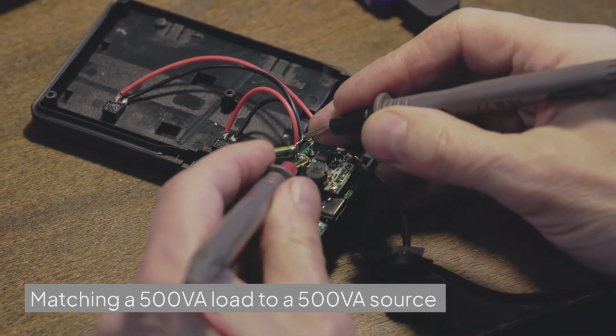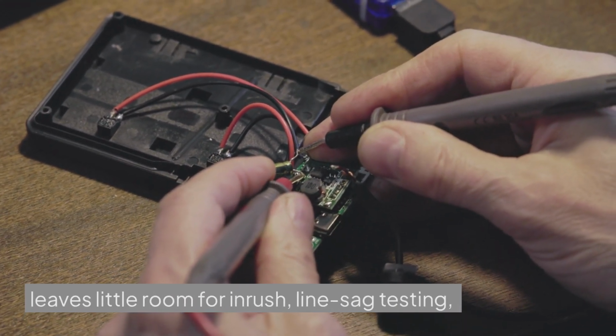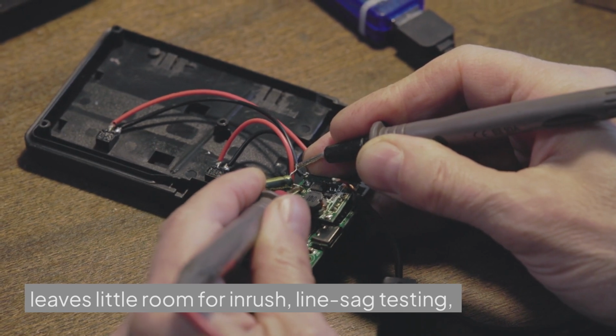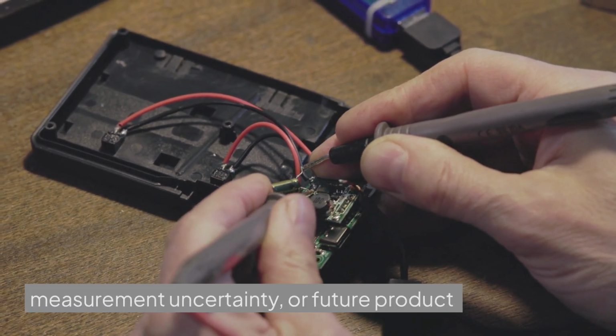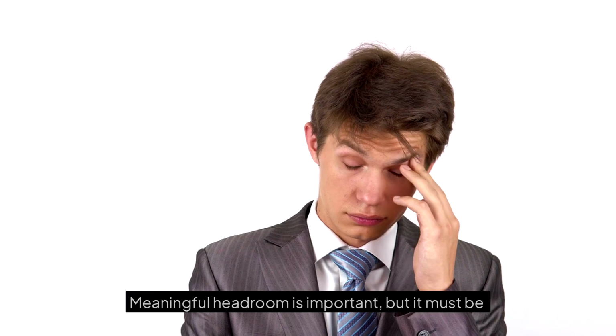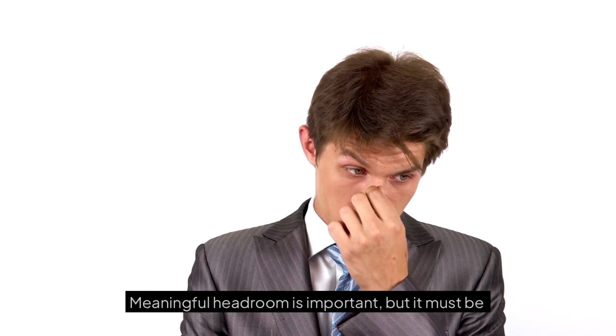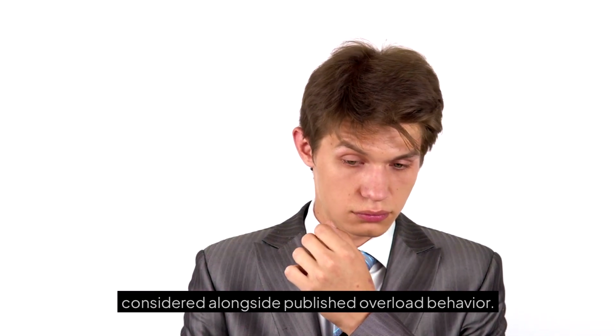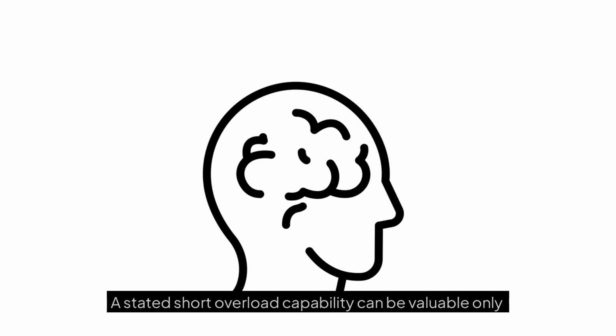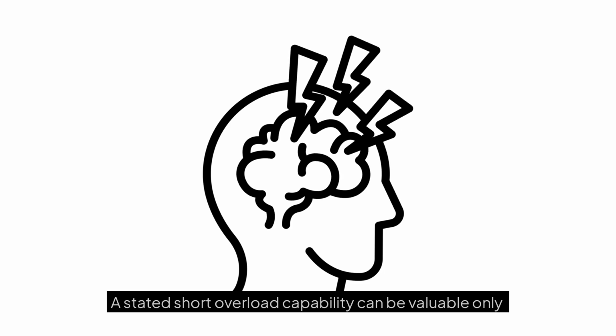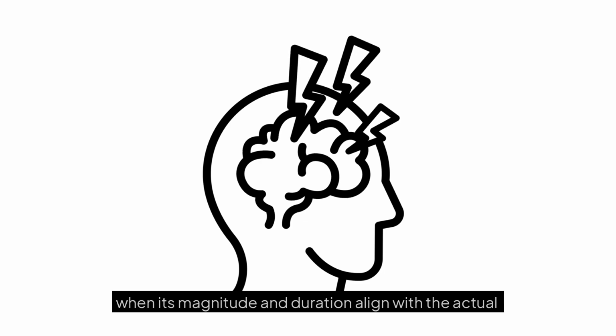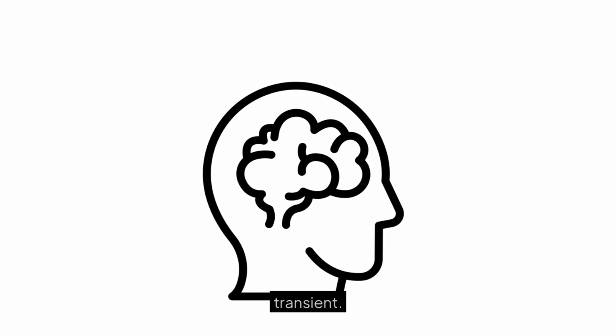Matching a 500 VA load to a 500 VA source leaves little room for inrush, line sag testing, measurement uncertainty, or future product variants. Meaningful headroom is important, but it must be considered alongside published overload behavior. A stated short overload capability can be valuable only when its magnitude and duration align with the actual transient.